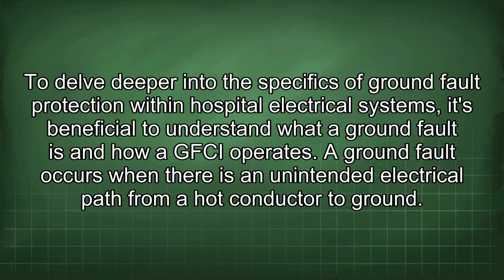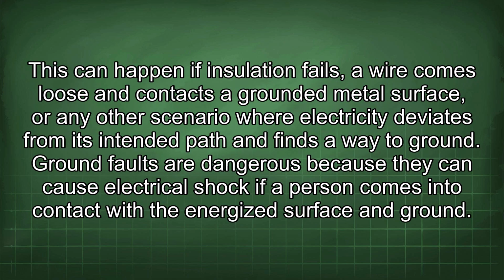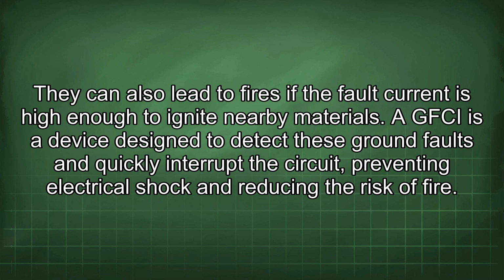To delve deeper into the specifics of ground fault protection within hospital electrical systems, it's beneficial to understand what a ground fault is and how a GFCI operates. A ground fault occurs when there is an unintended electrical path from a hot conductor to ground. This can happen if insulation fails, a wire comes loose and contacts a grounded metal surface, or any other scenario where electricity deviates from its intended path and finds a way to ground. Ground faults are dangerous because they can cause electrical shock if a person comes into contact with the energized surface and ground. They can also lead to fires if the fault current is high enough to ignite nearby materials.